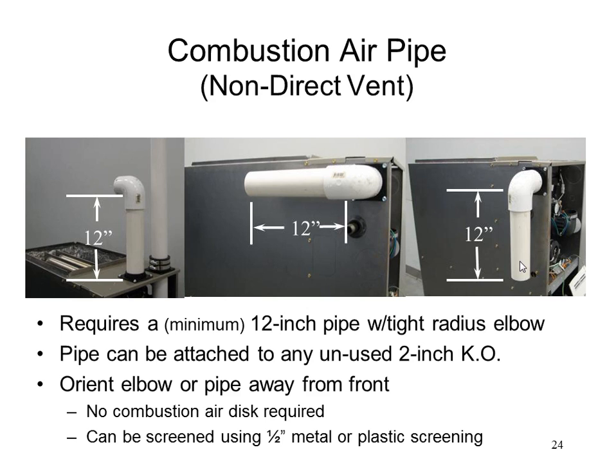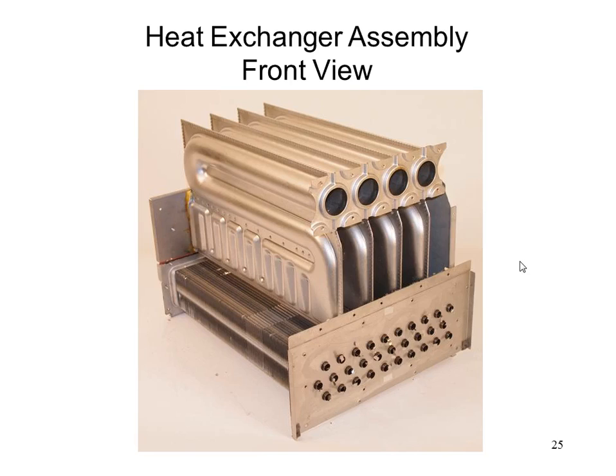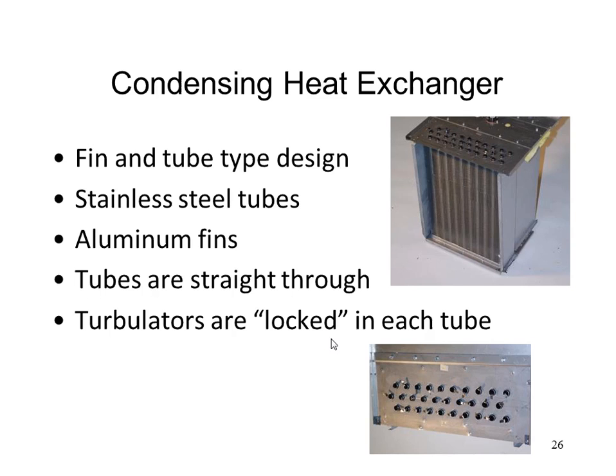But you could do a single pipe if you had to. That's the heat exchanger I showed you before. It's a little bit different angle view. You might be able to see it a little better. So these are all the fins that are on this guy here. And you could probably see those little turbulator tabs sticking out of the tubes there. So you pull those tabs out, it'd be a corkscrewed piece of metal going through there that causes turbulence and hence better heat transfer. That's just kind of describing that for you.